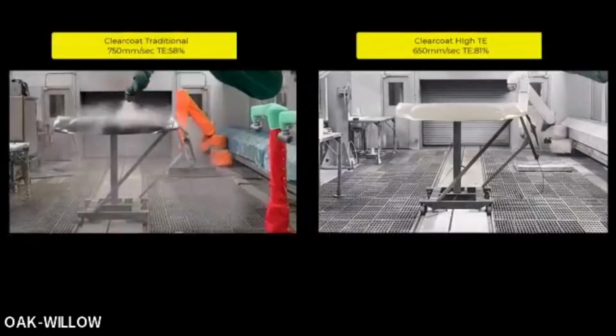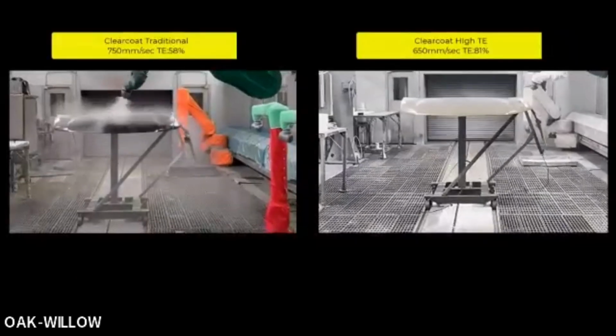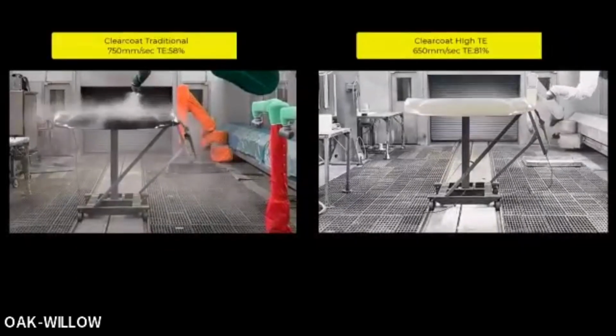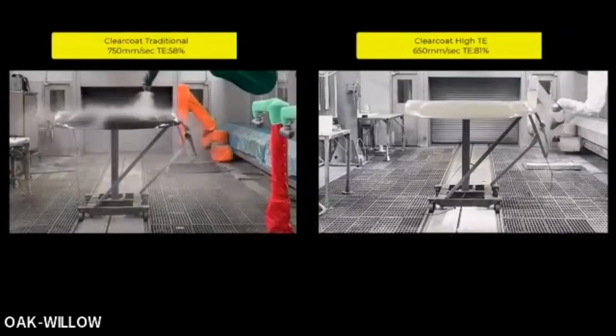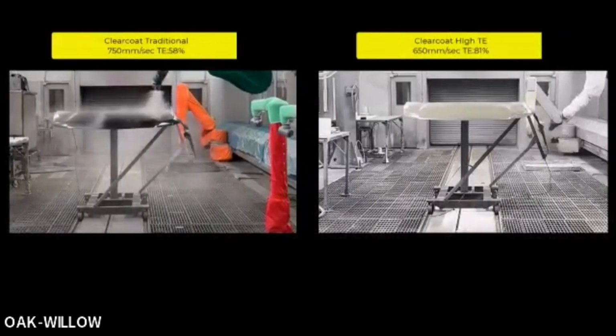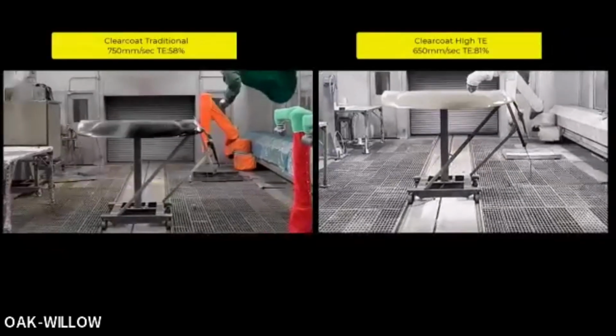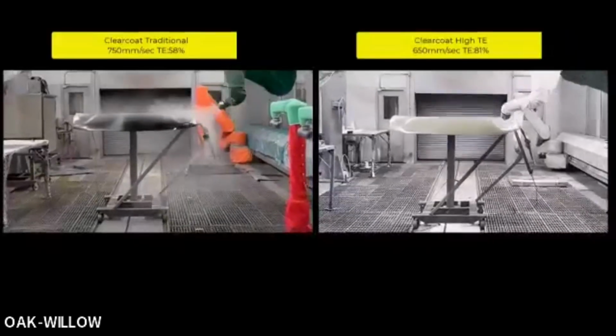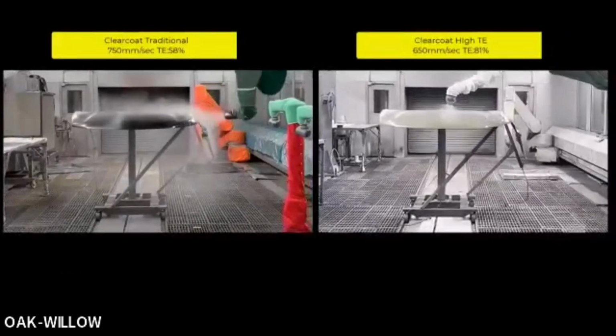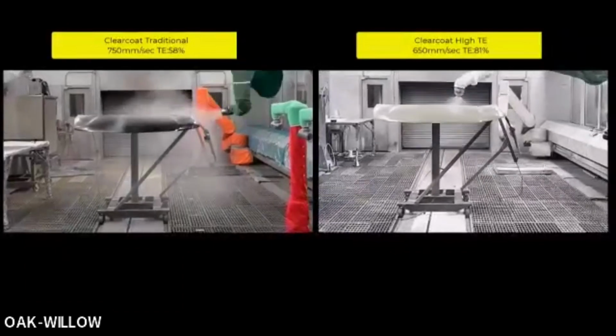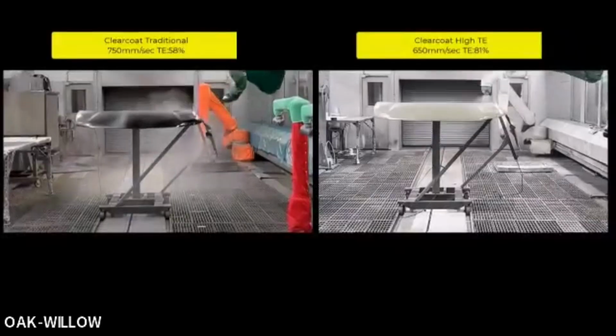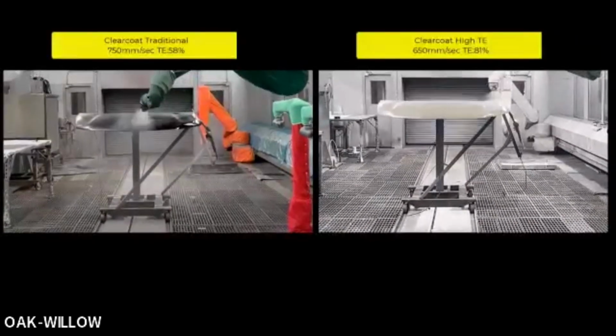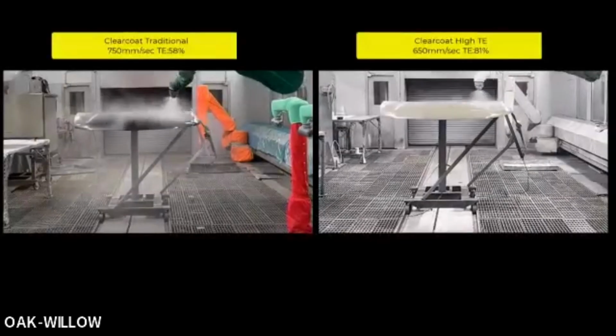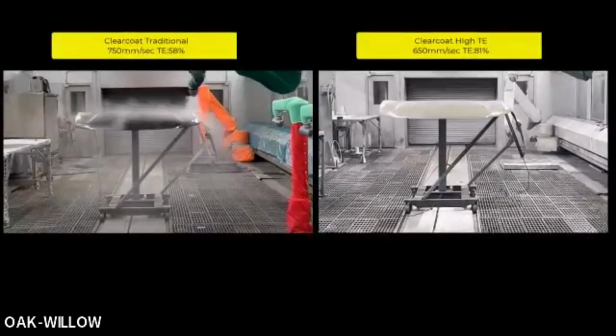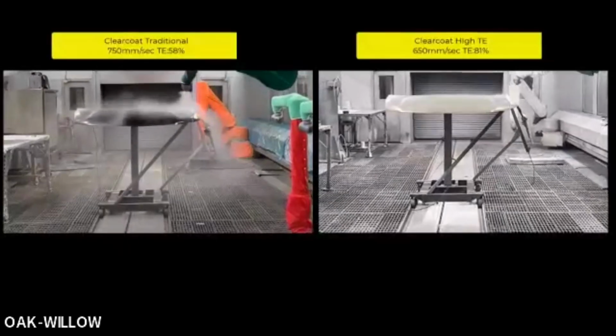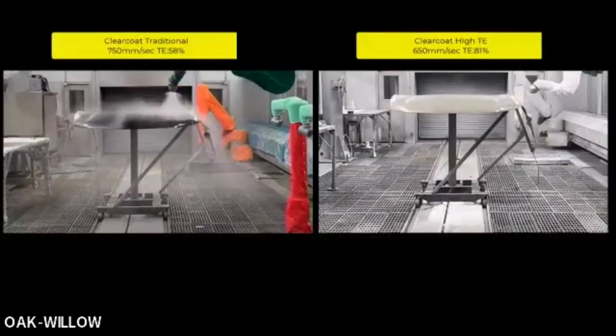So one variable we typically don't utilize is the booth relative humidity set point. If you think about a wet scrubber, asking for a lower humidity set point would mean upsizing our cooling coils, piping systems and pumps, maybe even adding a chiller, because there's more moisture to condense out of the air. But with a dry filter scrubber, you won't pay that capital or operational penalty from changing your booth humidity set point. We haven't rerun the DOE through the color palette with lower humidity yet, but it's a variable we can keep in our back pocket if we need to.